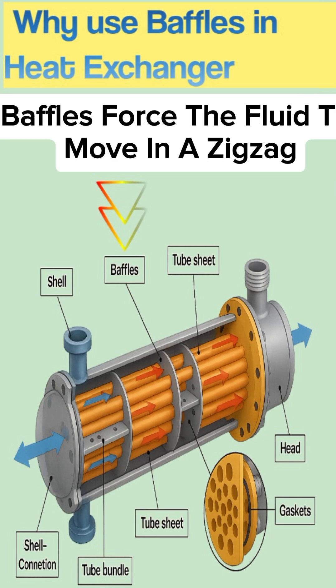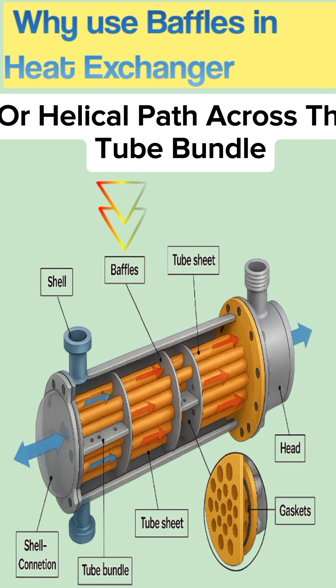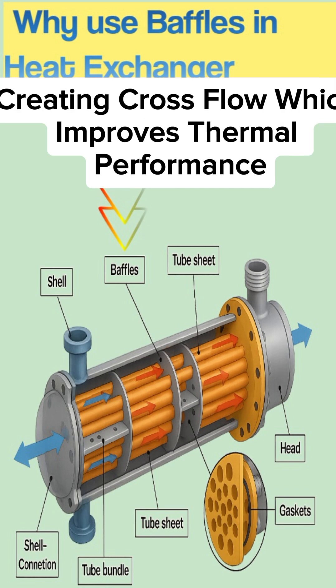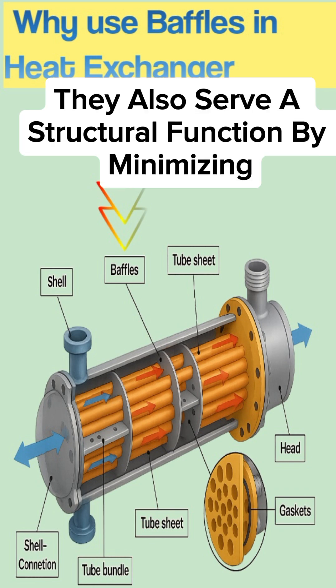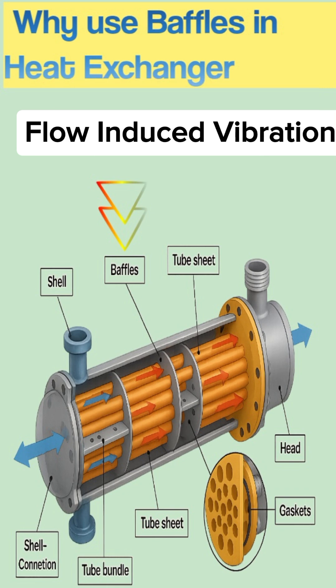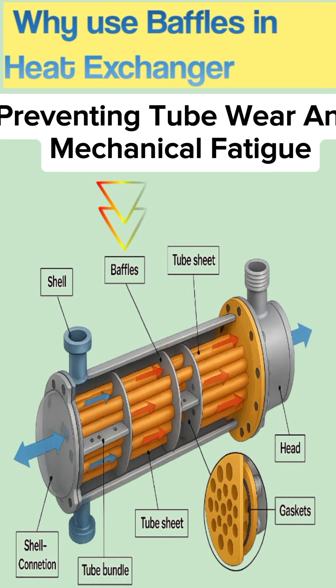Baffles force the fluid to move in a zigzag or helical path across the tube bundle, creating cross flow, which improves thermal performance, temperature uniformity, and tube support stability. They also serve a structural function by minimizing flow-induced vibration, preventing tube wear and mechanical fatigue.